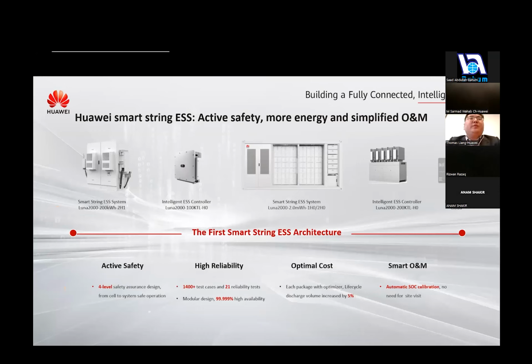So the last part is about our latest product, the Luna2000 200 kWh 2H1 battery solution. We can provide two types of battery solution. One is a 200 kilowatt hour solution. Another is a big size 2 megawatt hour battery solution, which are used in different scenarios. But all those products share the same technology and design concept. So we choose the modular design, and we can provide active safety and multi-level, full-level protection for the whole system.